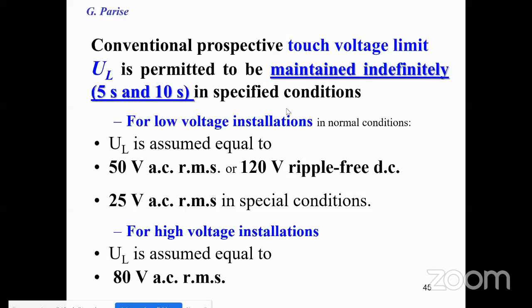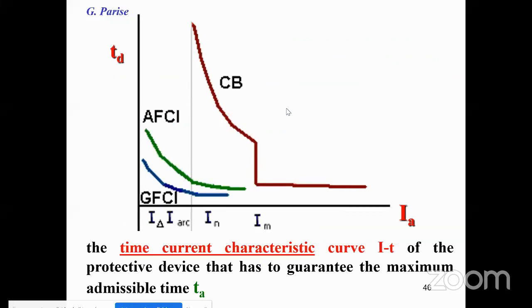Conventionally, I showed previously that the touch voltage limits permitted to be maintained indefinitely, that is, more than 5 seconds and 10 seconds, are 50 volt, 25 volt for special conditions, and 80 volt for high voltage applications. So we discussed the importance of the circuit breaker for TN systems, but residual current devices are always mandatory for additional protection, also as basic protection.